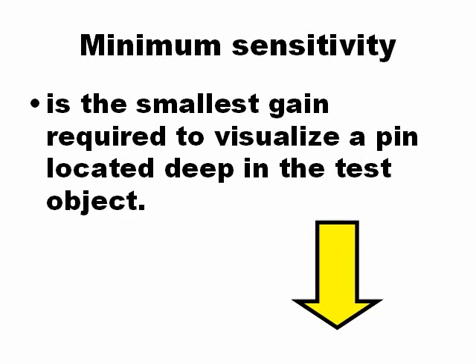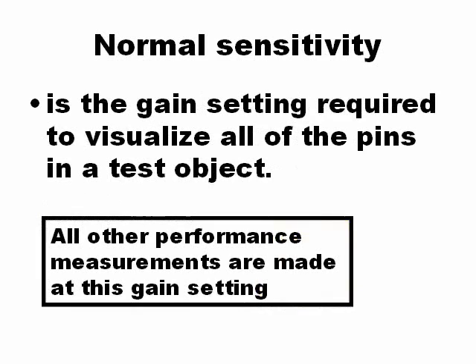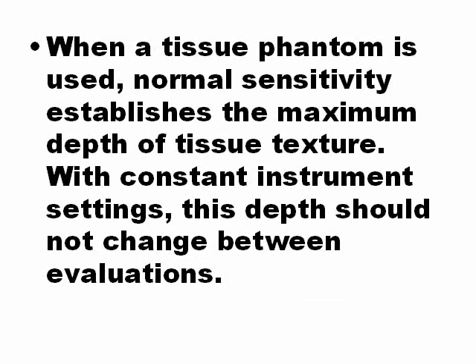Minimum sensitivity is the least gain that you need to visualize a pin located deep in the test object. Normal sensitivity is the gain setting to see all the pins in the test object. All other performance measurements are made with the normal sensitivity. When a tissue phantom is used, normal sensitivity establishes the maximum depth of tissue texture. With constant instrument settings, this depth should not change between evaluations.